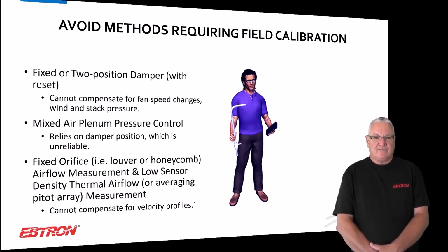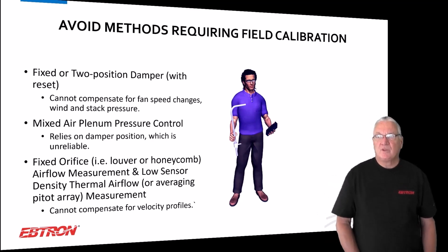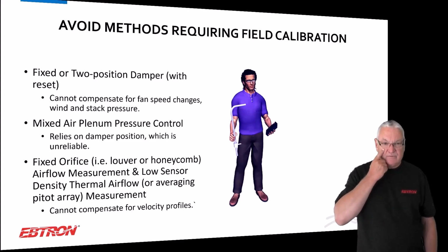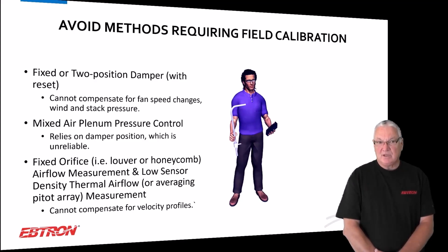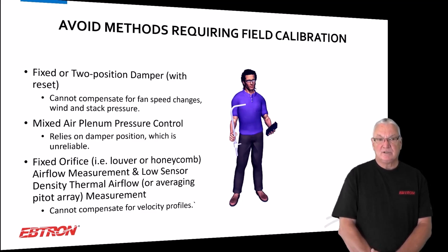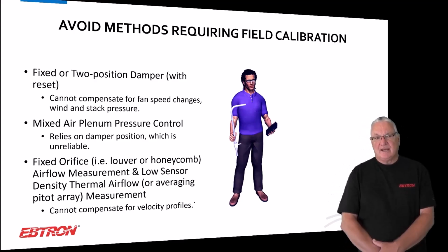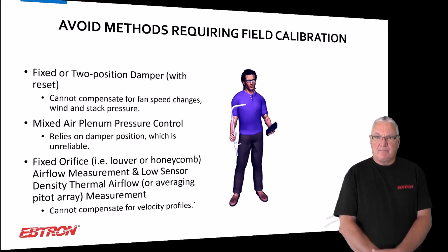Fixed orifice airflow measurement. So you're using the louver or something else as a fixed orifice. And one of our competitors does that. On an intake system, those are very, very low pressures. It's like saying I'll put a one sensor flow meter in an outside air intake, or two sensors. There are massive velocity profiles on intakes. I've seen 10-to-1 velocity profiles on intakes, and they move, they vary, they're not always the same. So if you have velocity profiles, you have pressure profiles.